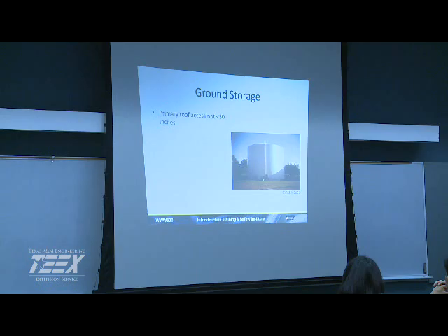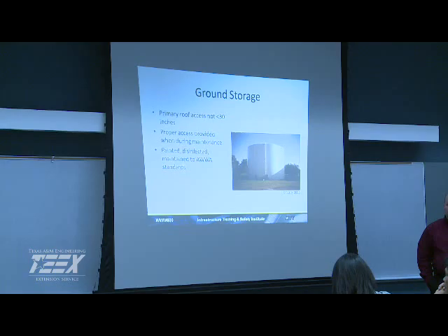So ground storage is very important. We need to make sure that we have roof access, not less than 30 inches if it's an old tank. We need to see about having it retrofitted so that we can have proper entry into it. Maintenance, how often are we doing our maintenance? I know y'all are looking at 5-year cycles, is that correct? We were doing a lot of 1-year cycles. We actually had people go into our tanks to do cleanings and videotape and stuff like that. Most of the time, that's 5 years like the documented. Mm-hmm. Most of these guys are. Yeah, and you got to do visuals real frequently, but you got to actually take them out of service every 5.